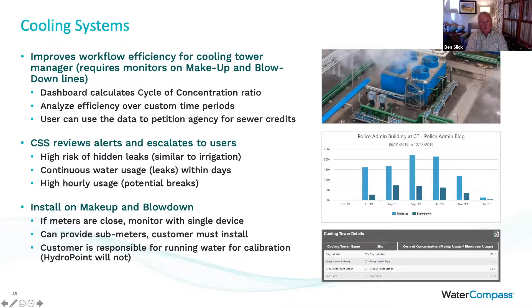Another benefit of Water Compass tracking makeup and blowdown is this: if there aren't deductive meters attached to blowdown, you're paying a sewer charge on every dollar of water read by the makeup meter — even though at least half of that water may be evaporating in the cooling process. Why pay sewer charges on 100% of that? This is a great way of capturing data to support a conversation about mitigating sewer charges on blowdown.